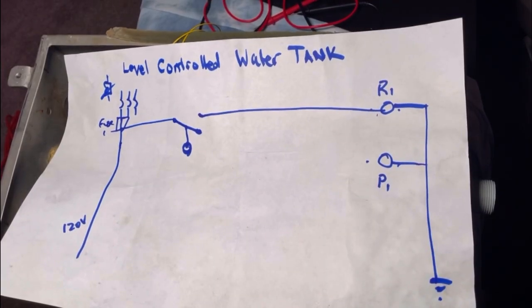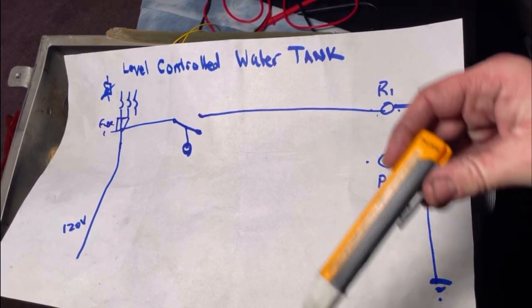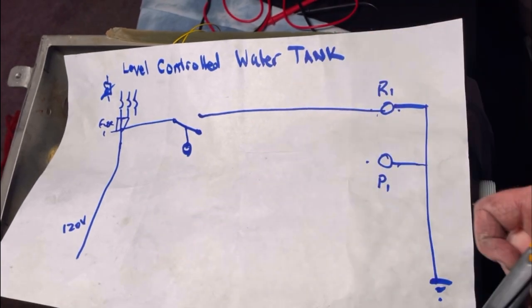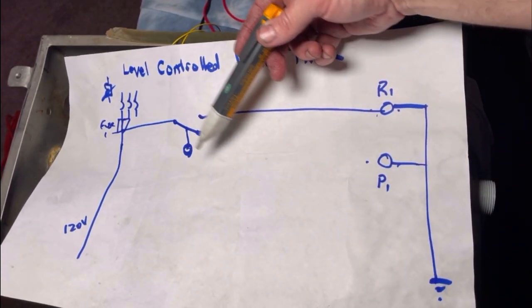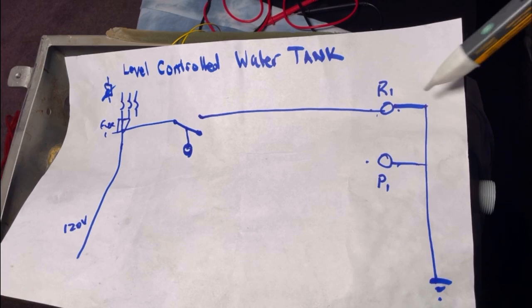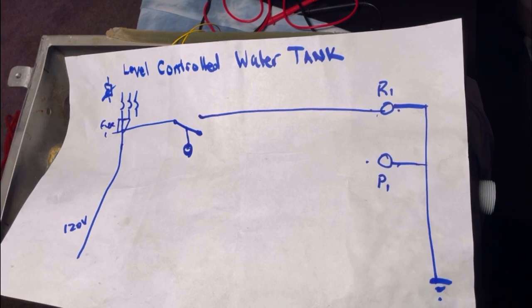In order to verify that I got the hot and neutral correct, what I'm going to do is pull out this relay and use this device. It's a tick tracer, and I'm going to make sure that this side of the circuit is hot and this side is neutral. The reason I have to do that is because I'm just using a random extension cord, and I'm not 100% sure that I have the right side. Usually the neutral has like an extra line on the insulation, but just to be sure, I'm going to do it this way to remain safe.